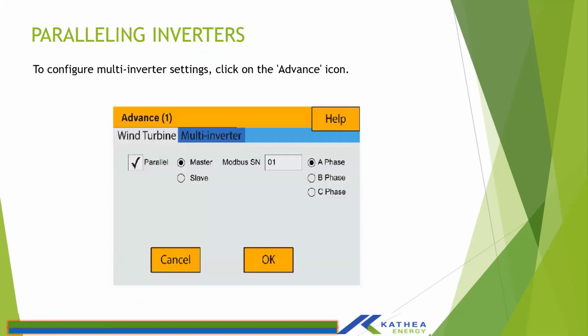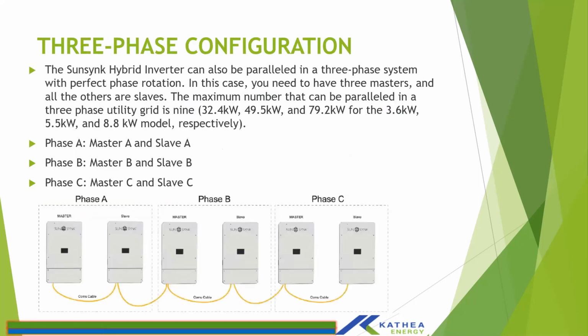So for phase A, you would have master and slave, and then when you go to phase B, you select master, and your second phase will be phase B, and the slave you would also select as phase B. The same for the third phase, which is C. Your master and slave will also be selected on C phase. And then the rule of thumb, the rule of construction, is the same as for a single phase: same battery bank, different distinct Modbus IDs. On the specific phases, the master should be the middle one if you have 3 inverters, and all the rules are the same: same model, same operating software, and all that.